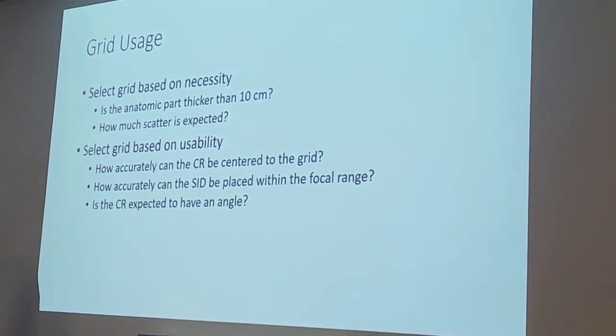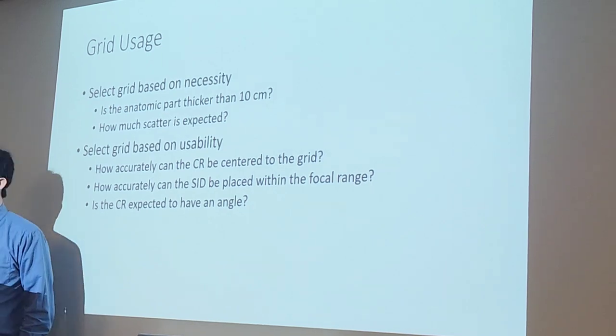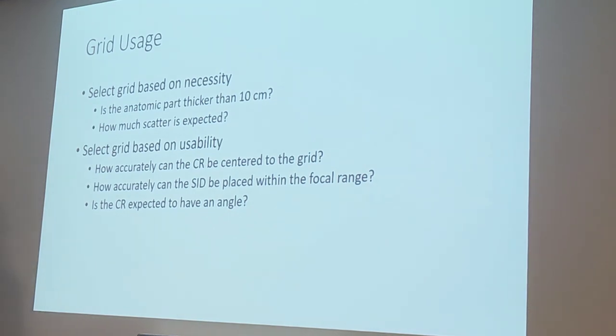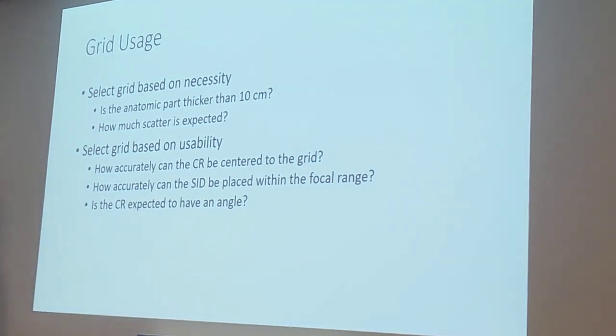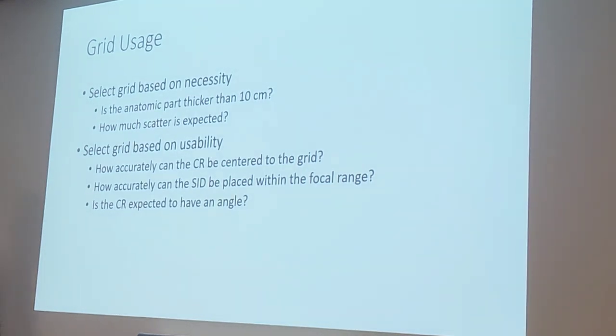I do have a question. Yes, Angelica. Near a Bucky, they usually always have a grid in there. Yes, in most of the machines, and even in the phone clinic, I think. And then when you go to clinics, places like Strawberry, Gulfgate, Aldine, I think MLK, using the old GE style machines, those do not have removable grids. Those grids are built into the wall Bucky, they're built into the table Bucky. You can't move them, you can't change them out. So unfortunately, you have to work with what you have. The newer machines do have grids where you can exchange them.